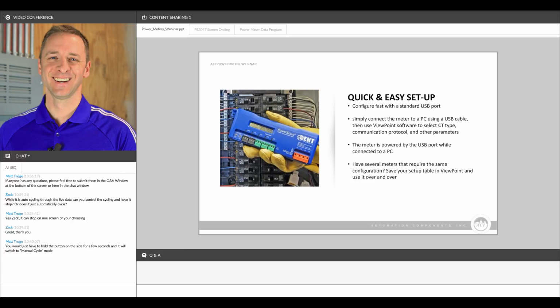One feature about these power meters, both the PS3037 and the PS24 that we'll be talking about in a minute, is that these can be set up and configured at your desk in your office. Some competitive meters, you have to set them up in the field while they're powered and operating. And obviously that can be problematic simply because these aren't always in the most conveniently accessible locations, especially if you're monitoring pieces of equipment. So these can be set up and programmed at your desk in the comfort of your own office.